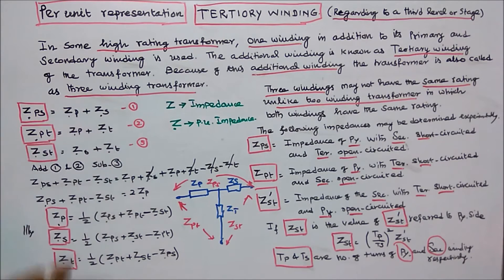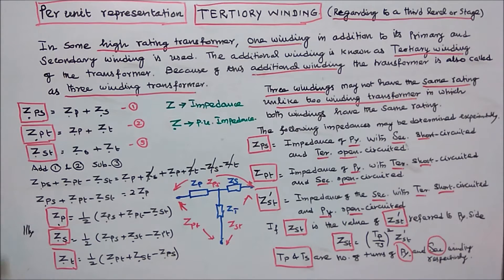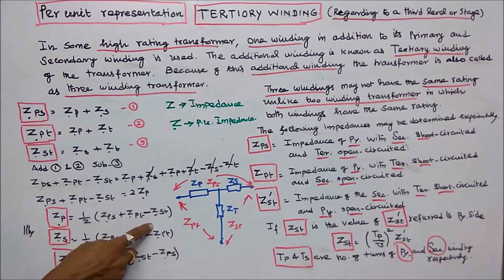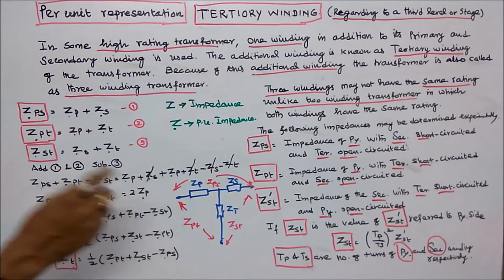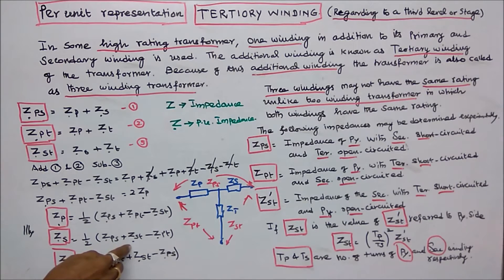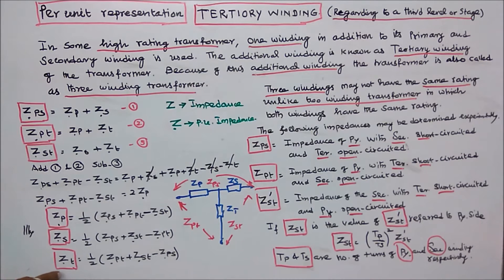We have three equations; by solving these three equations we can find the per unit impedance of primary, per unit impedance of secondary, and per unit impedance of tertiary winding. Per unit impedance of primary equals (1/2)(Zps + Zpt − Zst). Similarly, per unit impedance of secondary equals (1/2)(Zps + Zst − Zpt). Per unit impedance of tertiary winding equals (1/2)(Zpt + Zst − Zps).